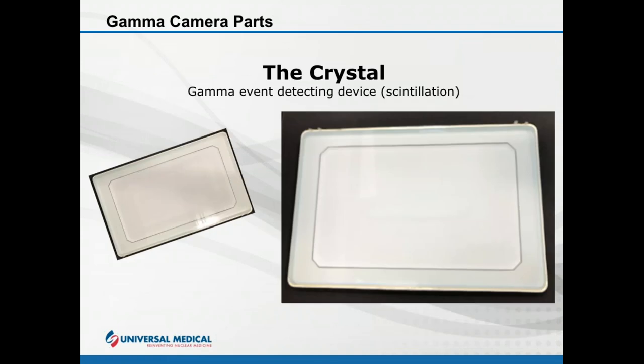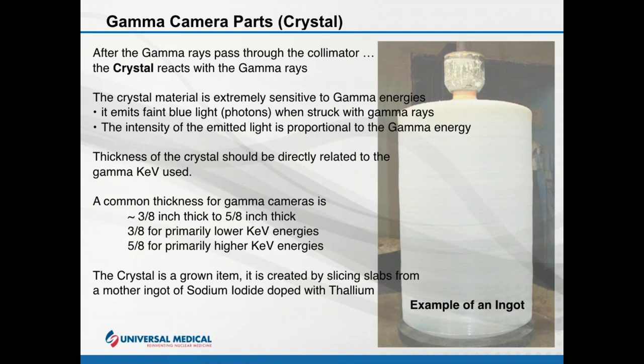The next device is the crystal. It detects the gamma rays and creates scintillations — as gamma rays pass through the collimator they react with the crystal, scintillating and creating photons with a very light blue hue. The number of photons created is proportional to the energy of the original gamma ray: high energy creates more light, low energy creates less. The thickness of the crystal must be considered — too high an energy has a probability of penetrating through without interacting, so higher-energy studies require a thicker crystal.